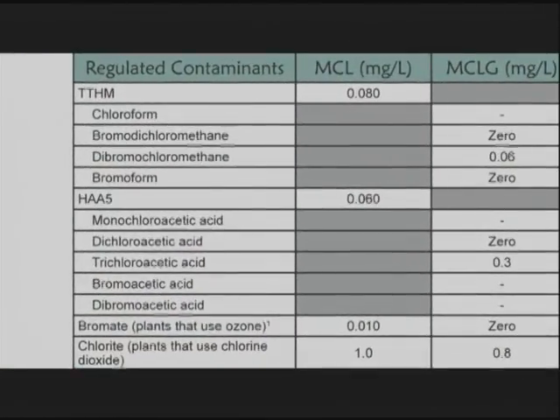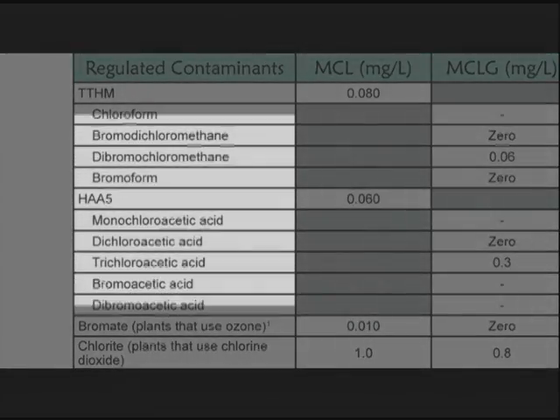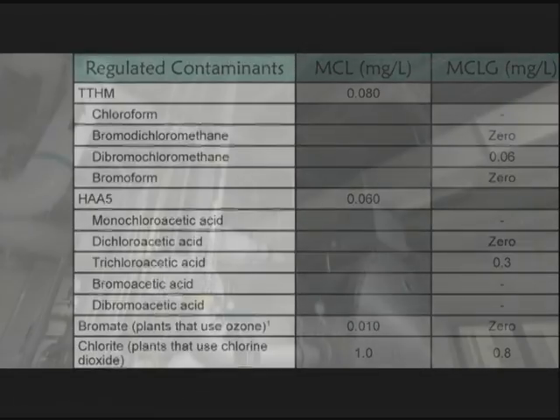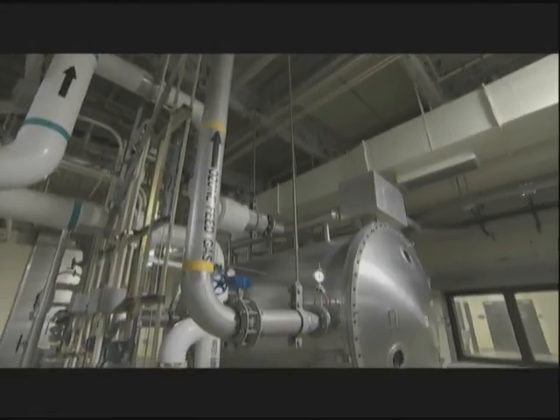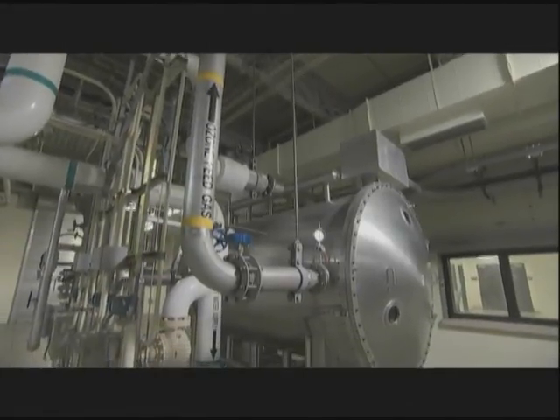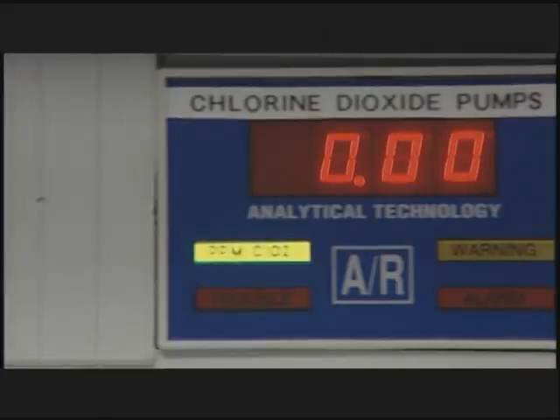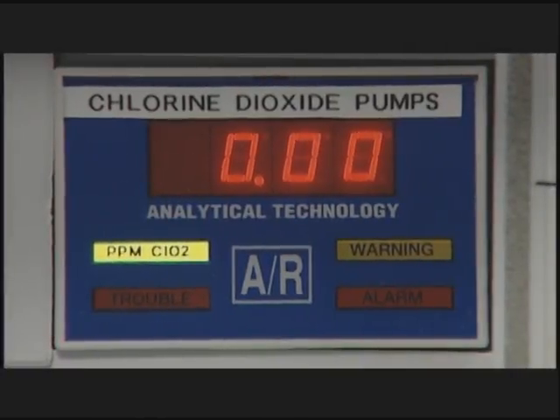Regulated contaminants under both the Stage 1 and Stage 2 rules include the four trihalomethanes and five haloacetic acids, along with bromate for plants that disinfect with ozone and chlorite for plants that use chlorine dioxide.